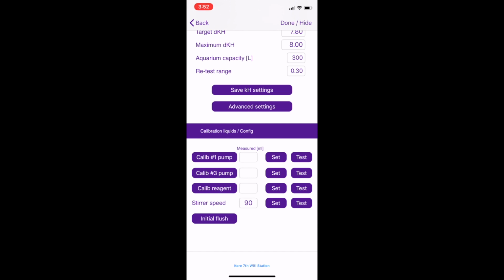Following that, at any time you can run a test. The test value should be identical to the measured value that you have set in here. You would do that for all 3 of them. I don't recommend calibrating a Kore7th until it has been running for about 2 weeks. When the units are new, they're prone to drift as they wear in, as the tubing settles, and due to a variety of other factors. If you calibrate it on day 1, you are essentially wasting your time because you will need to calibrate it again after a week or 2. So I wouldn't bother. Just run the unit and forget that you even have it for the first 1 or 2 weeks, and then spend your time calibrating it, and it will be much more stable and you'll save yourself a lot of time.